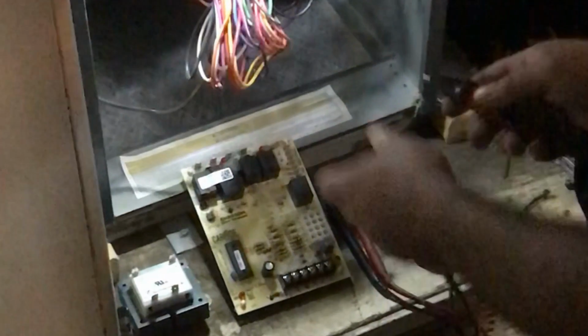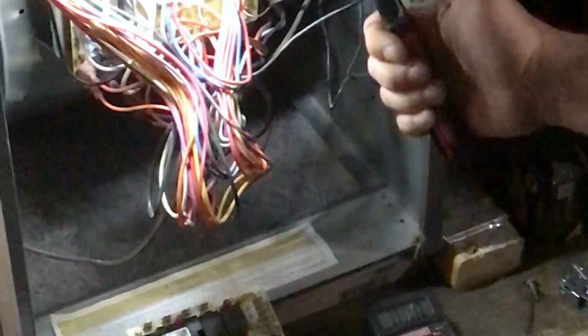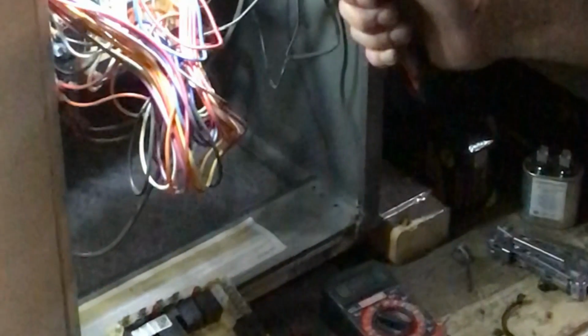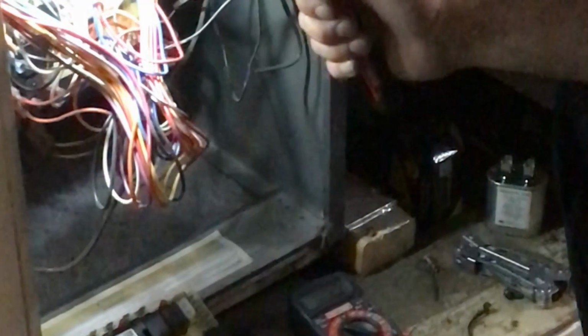An easier way, in case you're in a situation where you have a ton of wires in the way, you can isolate your cool speed wire and use a non-contact voltage tester. We got power to the fan. Now, obviously our fan's running, but if it wasn't, we got power going to it, bad fan motor.